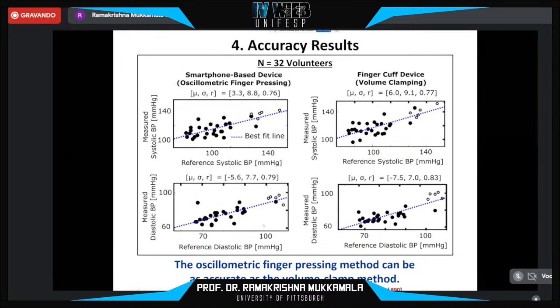Here are the accuracy results for the smartphone-based device and the finger cuff device against the reference arm cuff device. The smartphone-based device yielded bias errors of 3.3 and -5.6 millimeters of mercury for systolic and diastolic pressure, and precision errors of 8.8 and 7.7 millimeters of mercury over a 40 to 50 millimeter of mercury range of arm cuff blood pressure. These levels of errors are basically the same as the finger cuff device. So in sum, the oscillometric finger pressing method can yield calibration-free measurement of blood pressure with a level of accuracy comparable to cuff-based devices.